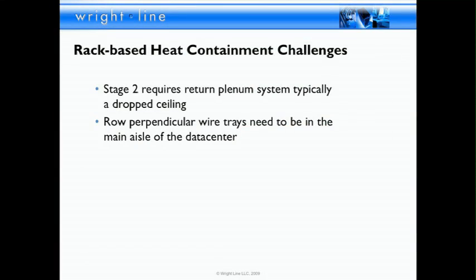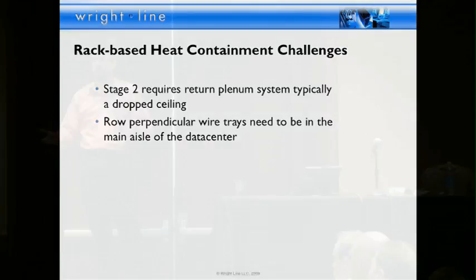Obviously, rack-based heat containment has challenges, like I said, nothing's without challenges. You need a return plenum. A lot of data centers don't even have a drop ceiling, let alone a return plenum, and is it rated? Those are some questions. And then how do you actually connect a rack up to the ceiling?